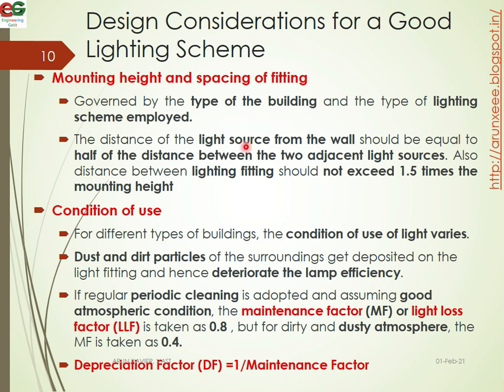The distance of the light source from the wall should be equal to half of the distance between two adjacent light sources. Also, the distance between light fittings should not exceed 1.5 times the mounting height.